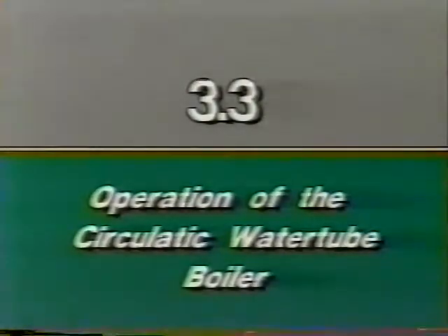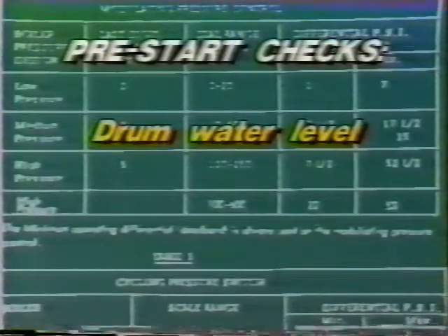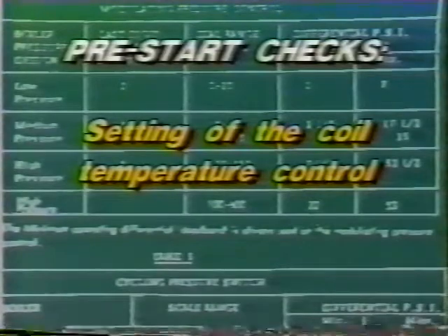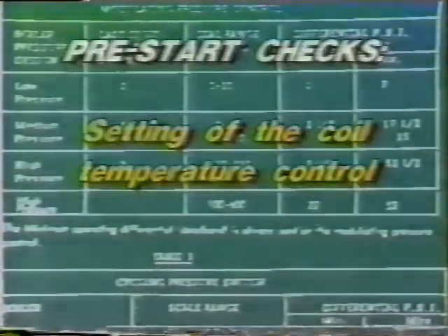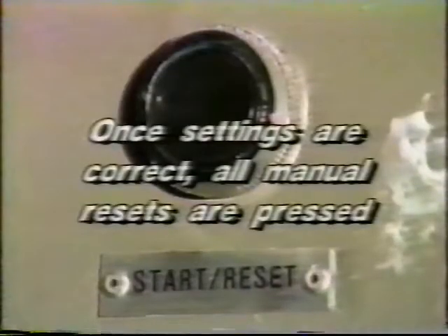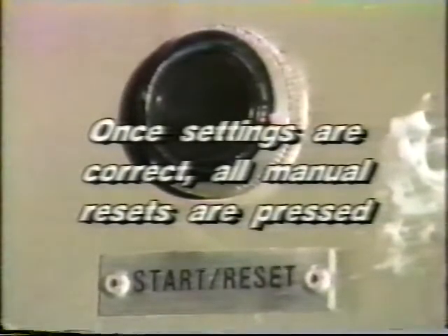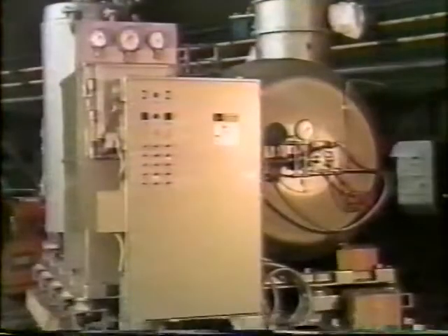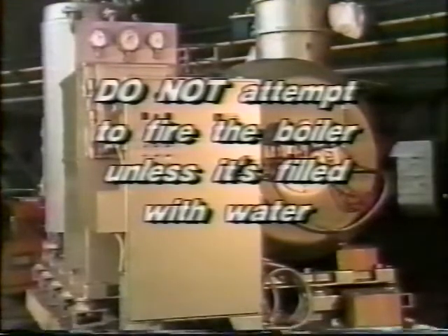Operation of the circulatic water tube boiler. Startup. Before attempting to start the circulatic water tube boiler, consult the operating instructions in the Vapor Technical Manual. The manual covers several pre-start checks, such as the following: modulator burner control dial setting, the cycling pressure switch, the drum water level, and the setting of the coil temperature control. Once these settings are correct and the boiler is filled, all manual resets are pressed. It's important to remember, do not attempt to fire the boiler unless it is filled with water.